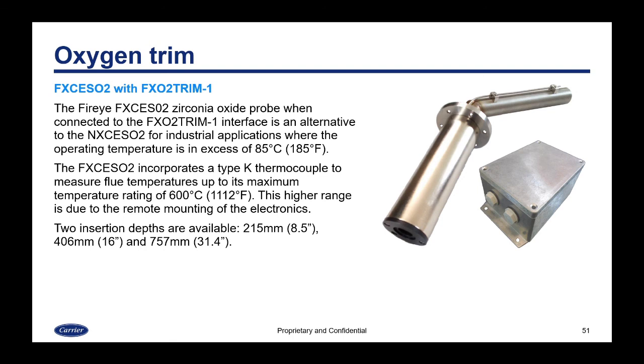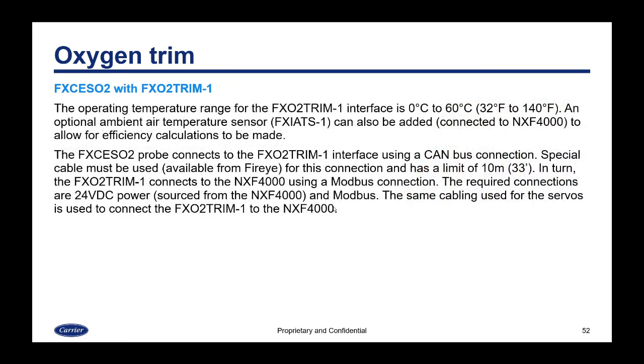The electronics in the NXCESO2 probe are mounted to the probe, whereas the electronics in this case are mounted in the FXO2TRIM, which is going to be mounted remotely. We have 3 insertion depths available here, 8.5 inch, 16 inch, and there's a longer 31.4 inch as well. The operating temperature range for the FXO2TRIM interface, and that's the electronics themselves, is the same as the NXCESO2 at 0 to 60 or 32 to 140. But since it's remote mounted, the ambient temperature at the stack is higher. An optional ambient air temperature sensor can also be added, just as with the other O2 trim option, to allow for efficiency calculations to be made.